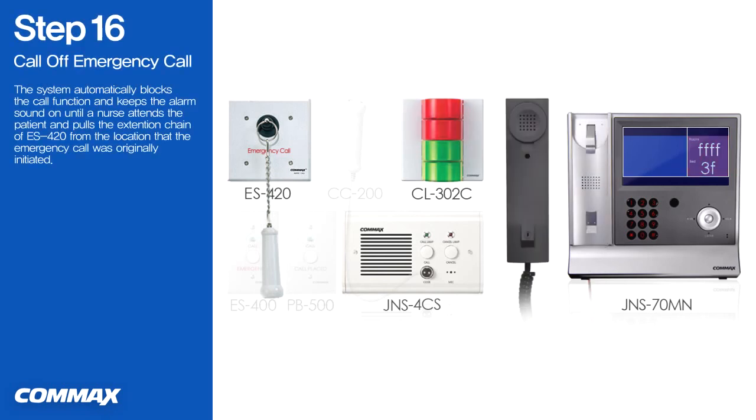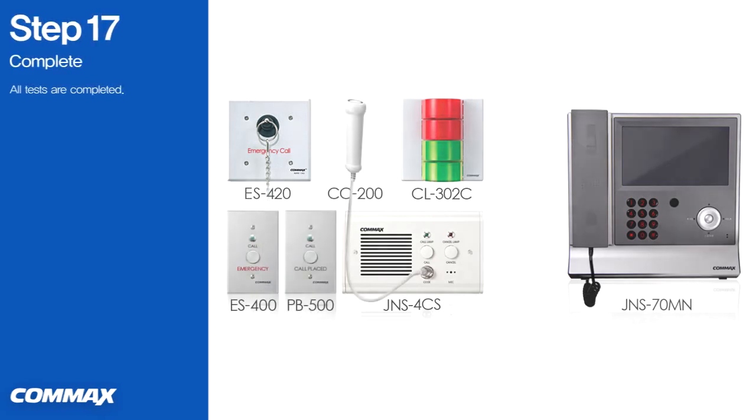Now the system automatically blocks the call function and keeps the alarm sound on until a nurse attends the patient and pulls the extension chain of ES420 from the location that the emergency call was triggered. All test procedures are completed.